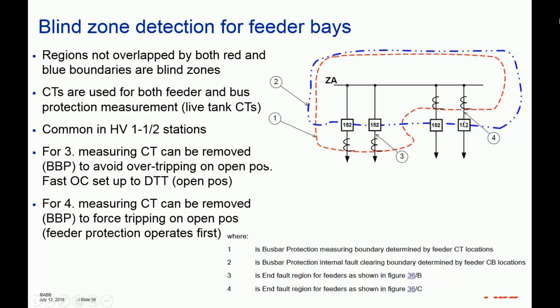You remove the CT connection internal inside the relay, then the bus protection will operate safely and quickly once the breaker is open. There will be a slight delay, but in this case, at least you don't have to wait for, for example, the breaker fail protection or any other backup protection, usually with time delay of 10 cycles or more to save the day. If you use this way, you can actually clear the fault on its own quickly.